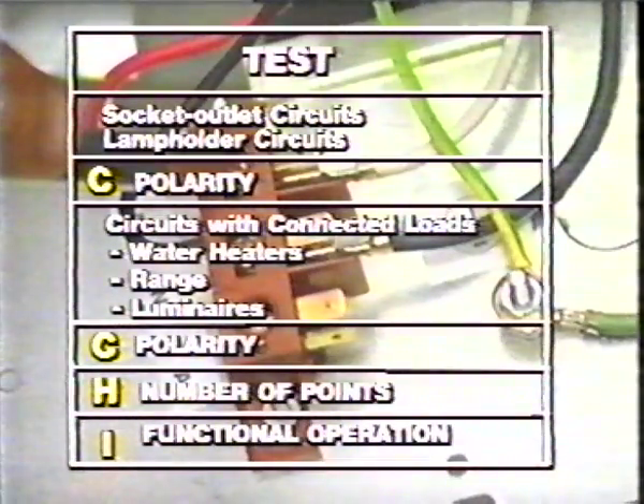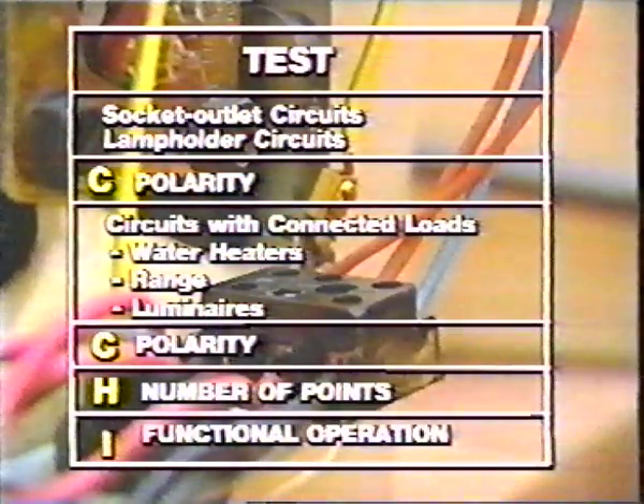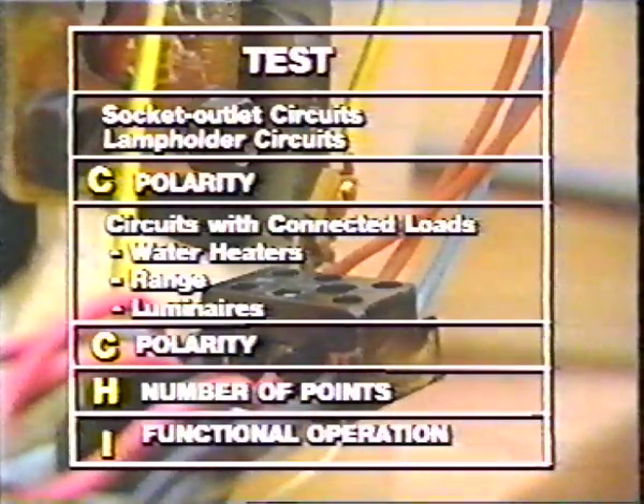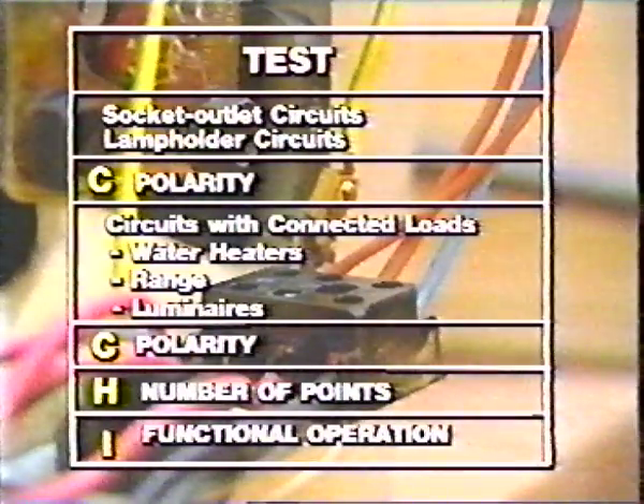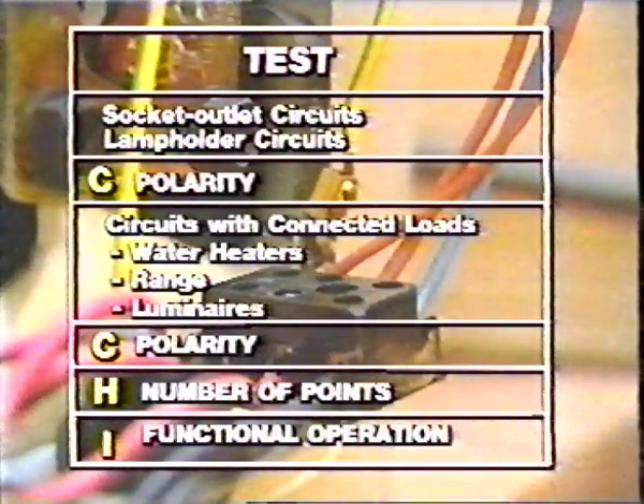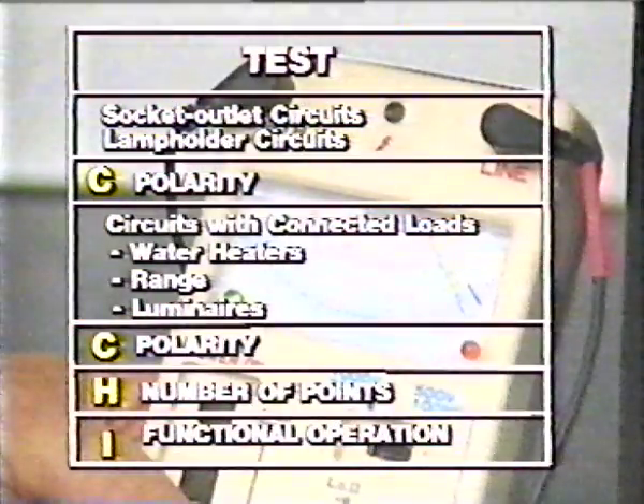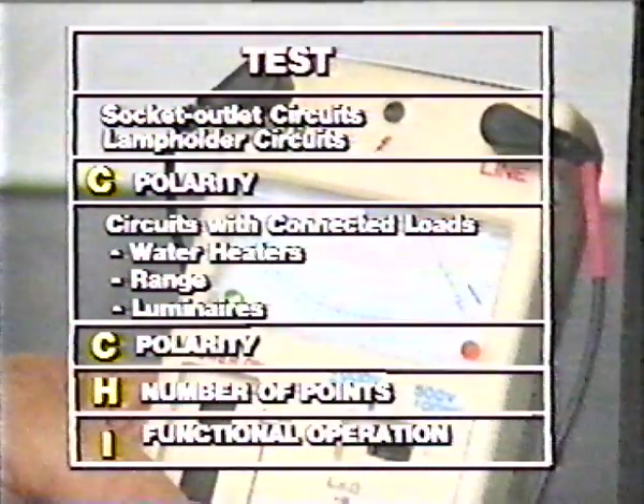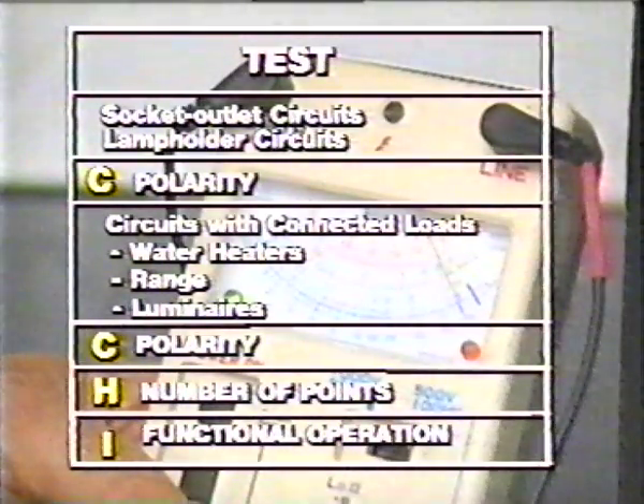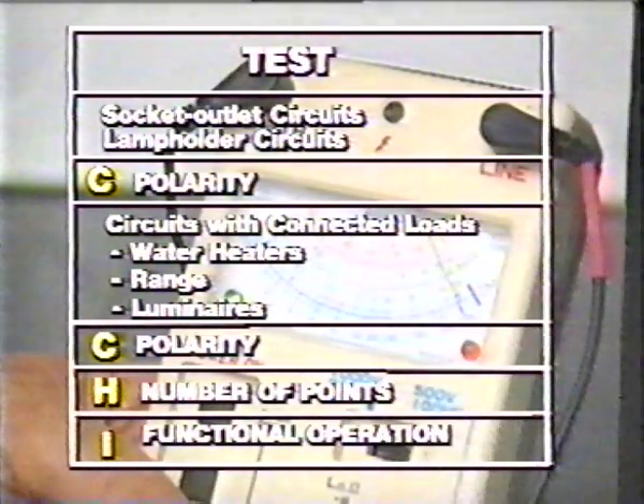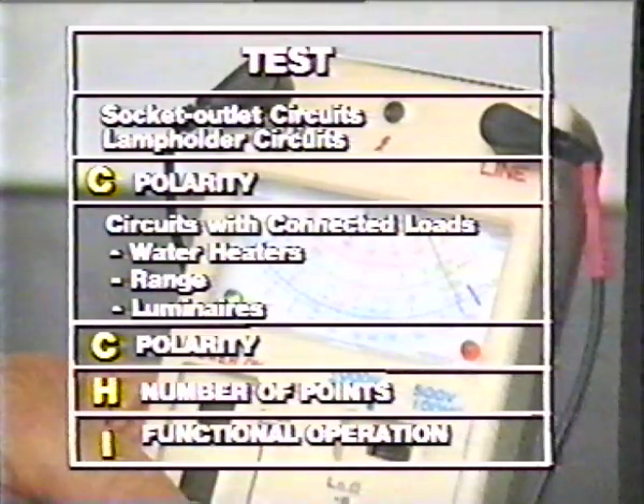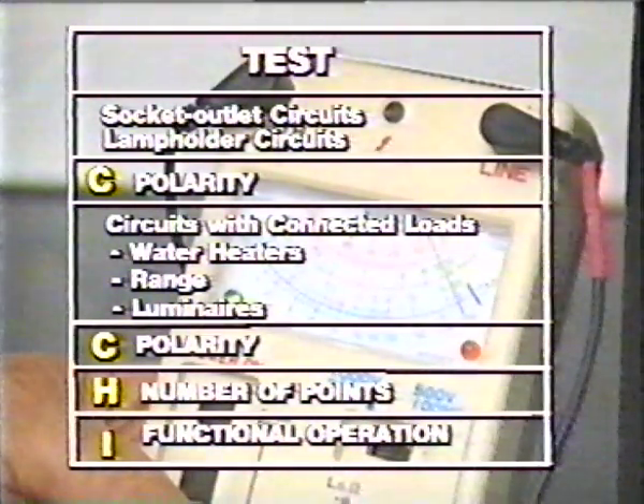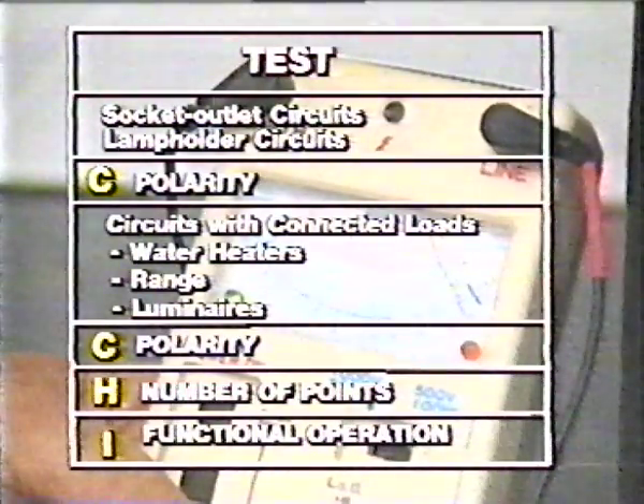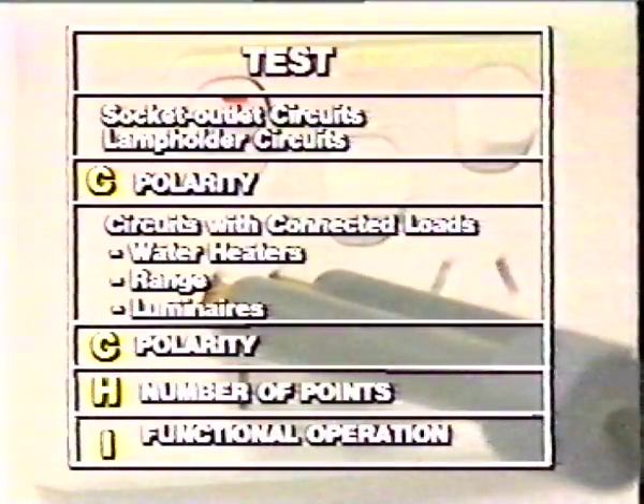In the case of fixed appliances, such as ranges and water heaters, polarity is tested by connecting an ohm meter between a known earth and the active and neutral terminals of the appliance, firstly with the switch on and then off. Correct polarity is proved if, with the switch on, active to earth indicates a typical resistance of 5 to 15 ohms, while neutral to earth indicates a short circuit. With switches off, active to earth should be an open circuit and neutral to earth a short circuit. The number of points connected to each lighting and socket outlet circuit is now determined as in test H.